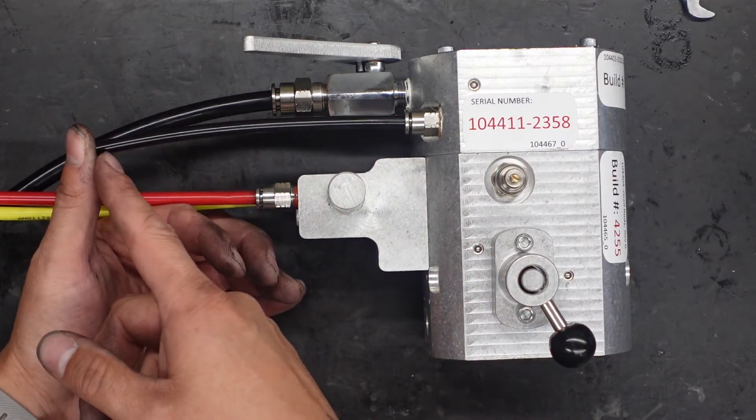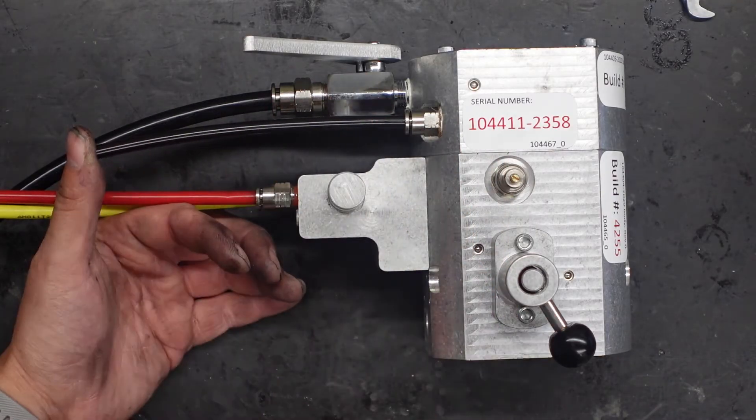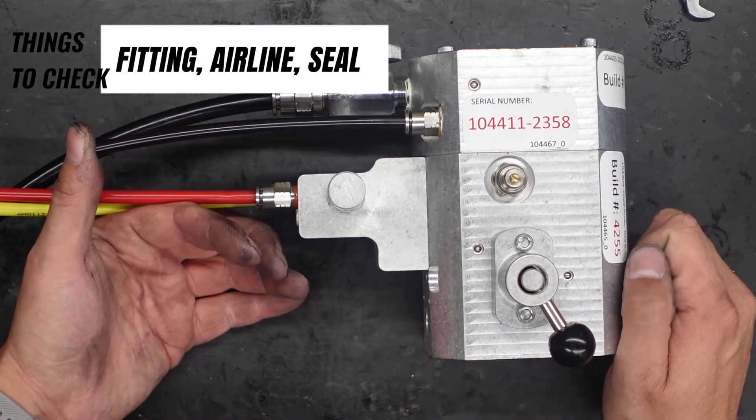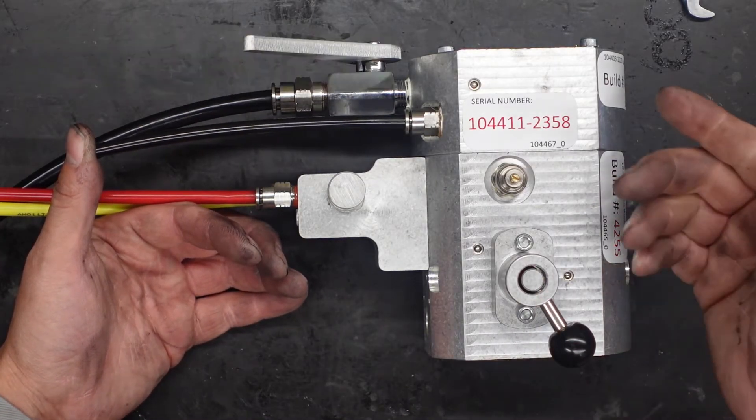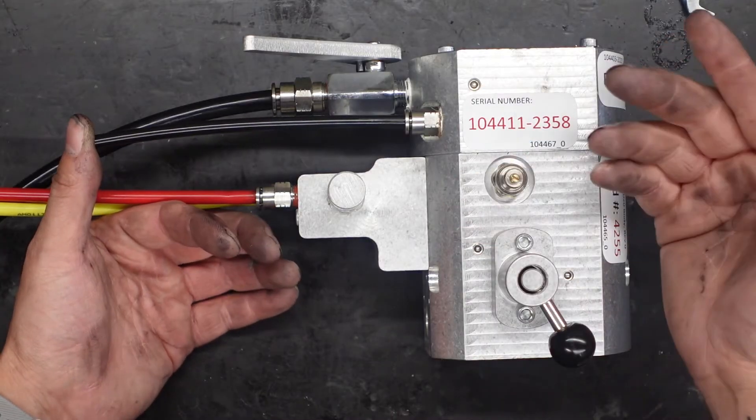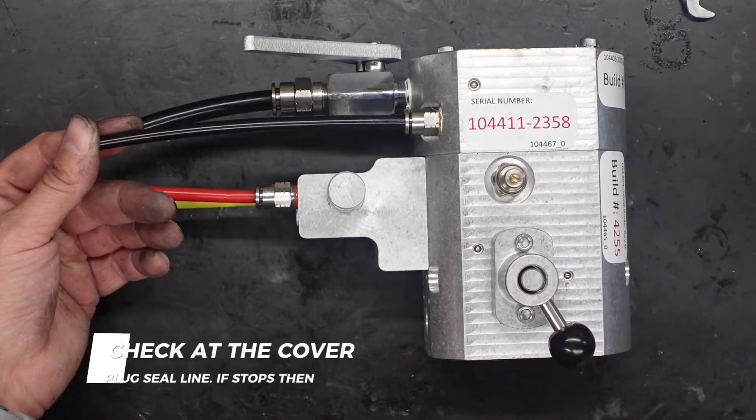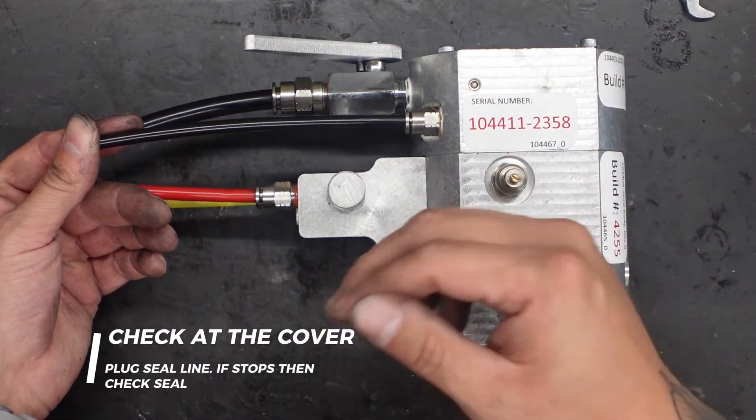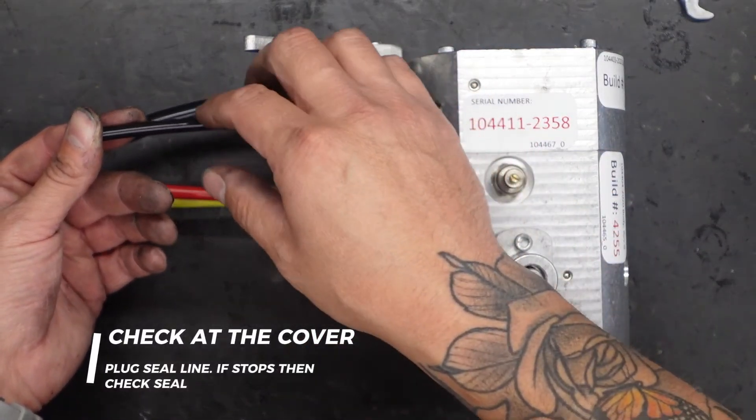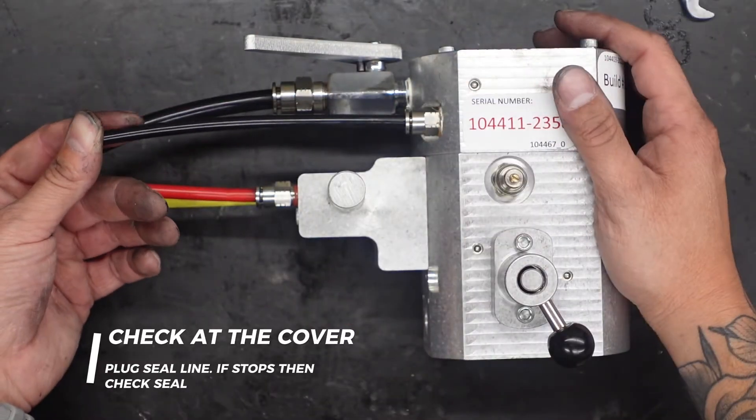So if that cycling stops here at the control box then it's an issue with something from here on up. It can be a fitting, it can be a hole in the seal, it can be a hole in the airline, a kinked airline, or all the above. So then you would have to go up to the cover itself and disconnect that airline there on the seal and check it.